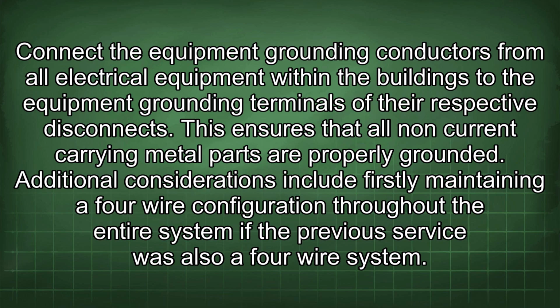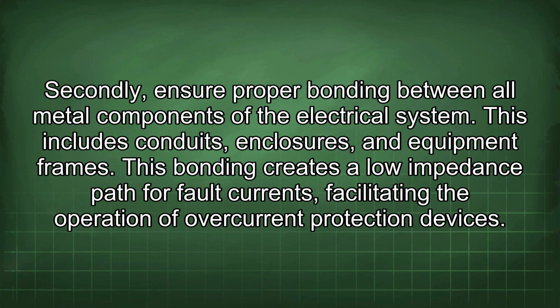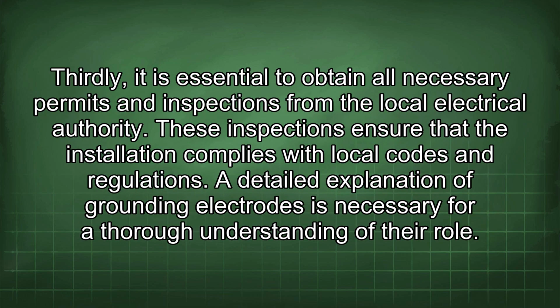Additional considerations include, firstly, maintaining a 4-wire configuration throughout the entire system if the previous service was also a 4-wire system. Secondly, ensure proper bonding between all metal components of the electrical system. This includes conduits, enclosures, and equipment frames. This bonding creates a low impedance path for fault currents, facilitating the operation of overcurrent protection devices. Thirdly, it is essential to obtain all necessary permits and inspections from the local electrical authority. These inspections ensure that the installation complies with local codes and regulations.